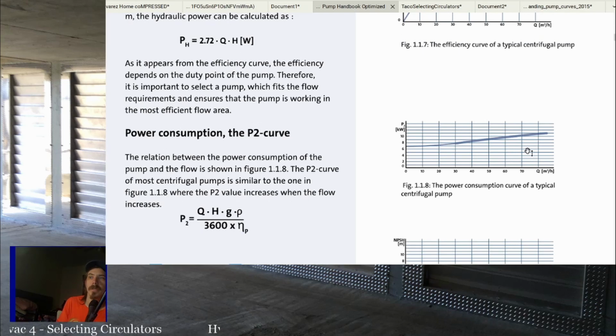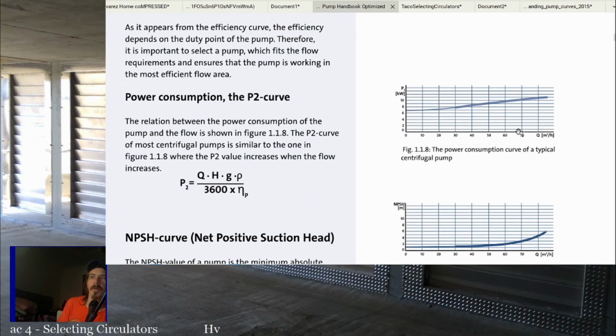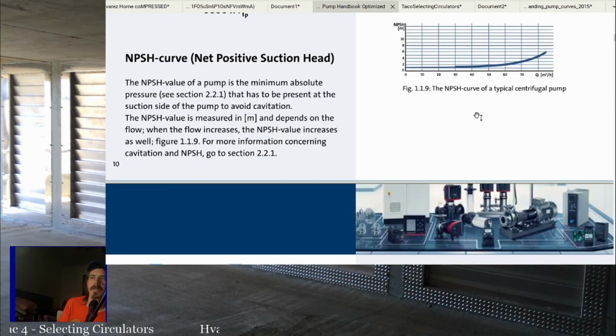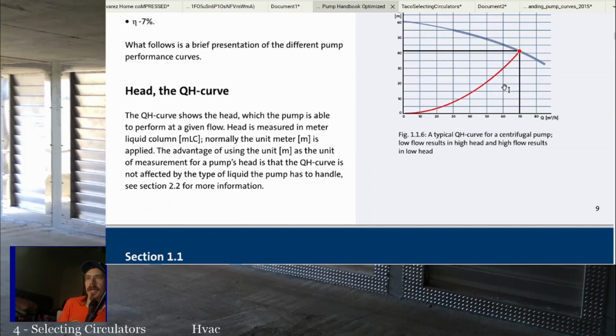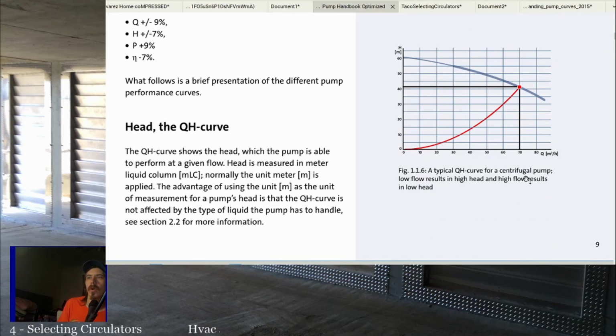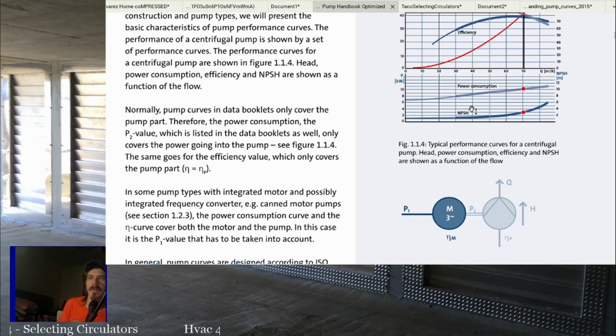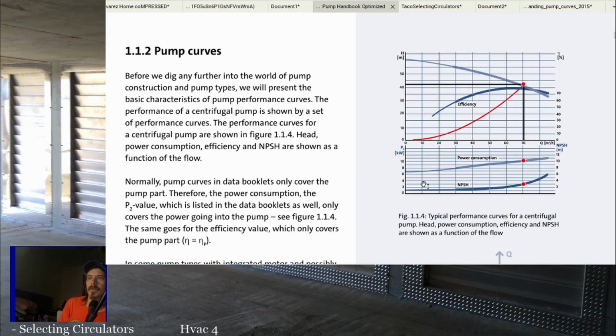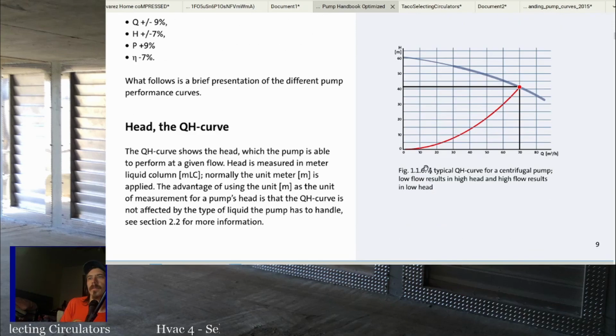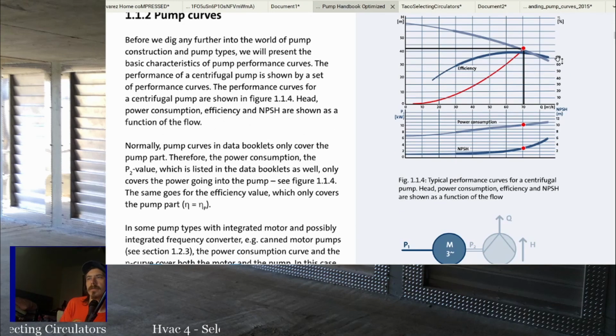And then power consumption. So the actual power consumption of the pump based on how much you're going. And then net positive suction head is basically where you need to be before you hit cavitation. So sometimes they'll put charts together that have all those curves on one chart, so you can have a good idea of, okay, what's my power consumption going to be, and my net positive suction head going to be at the operating point of the system right here. The efficiency, so you can see like this one, it's just a little bit past the best efficiency, and the head curve, how much head you're running at.